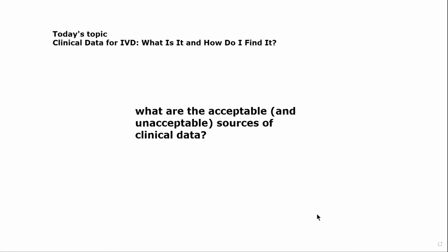We would use systematic literature review to identify sources of clinical data that have been published and meet those higher levels of evidence. We would steer away from any claims that have been put out. A claim is not the same as data. Your marketing claim may state our test is the fastest on the market or gets results 10 times faster than the other. If you don't have that data in a published data set, that would not be an acceptable source of clinical data. That's a marketing claim.